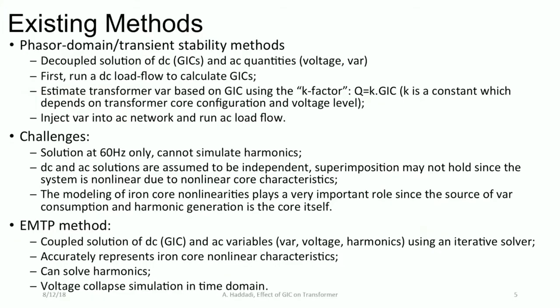EMTP is not bound by these limitations. We can solve the DC and AC components together without needing to make any specific assumptions regarding steady state. We can solve the dynamics of the GMD and the time-varying waveforms. We can accurately represent iron core nonlinearities and transformer topology, calculate harmonics using appropriate models in EMTP, and run voltage collapse simulations in the time domain.